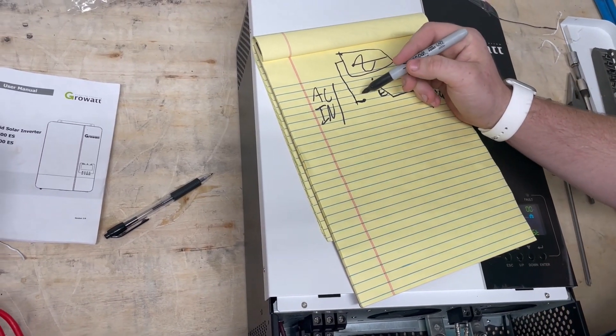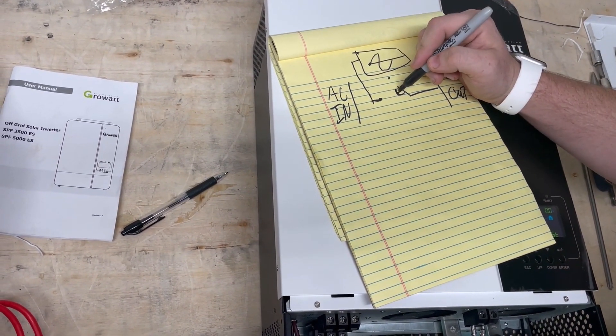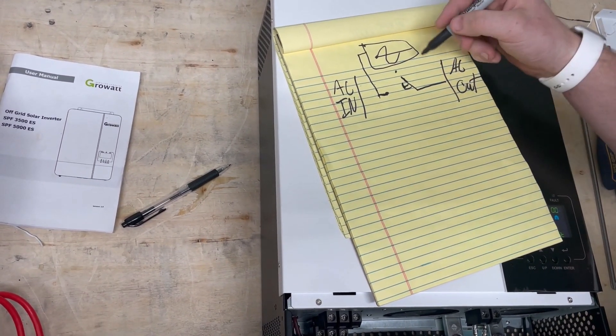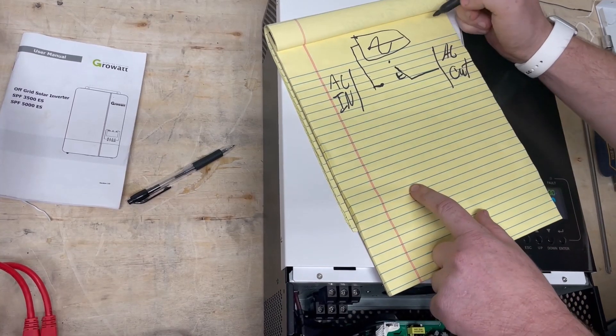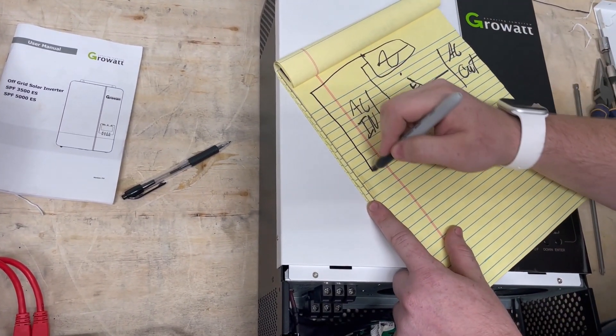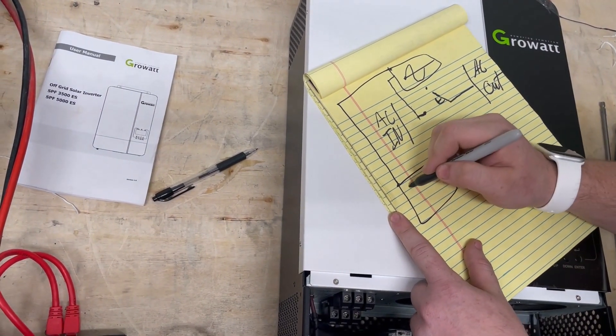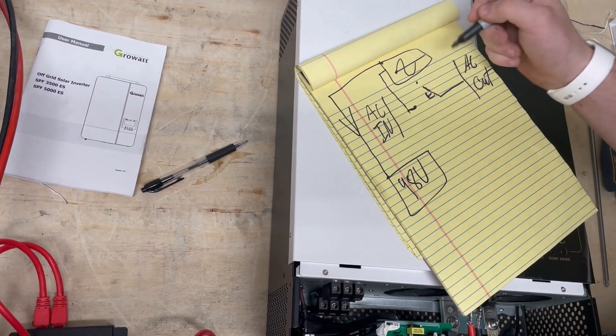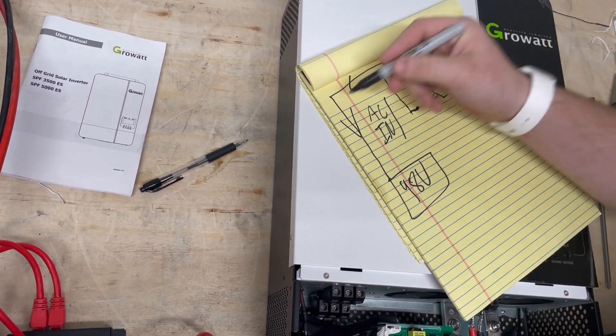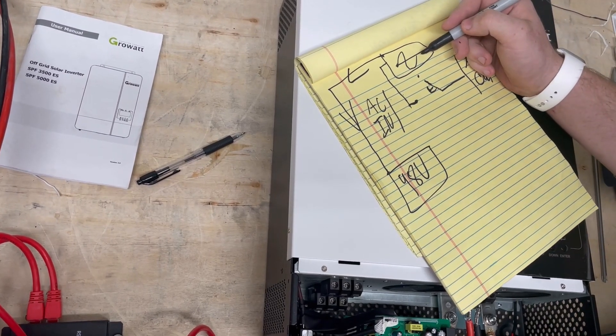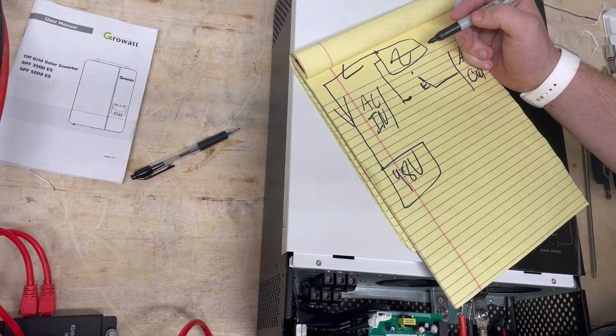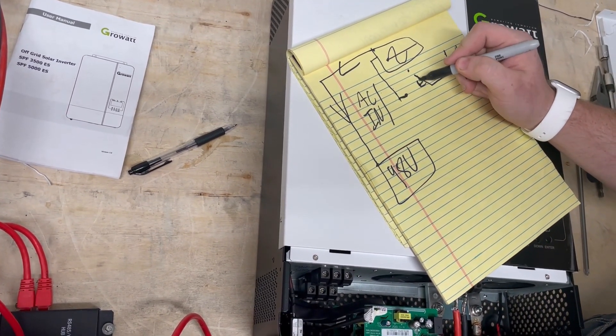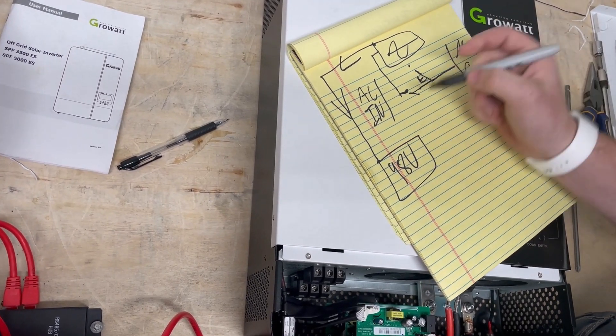The inverter is aware of AC in all the time. But if you're trying to run the inverter as a charger, this plugs to our batteries at 48 volts. To use this as a charger, it must pull from the grid to power that. In order to do that, it cannot be an inverter and a charger at the same time. So this relay is going to switch, and your power from the AC in, also known as your generator, is passing straight through from the generator to your loads.